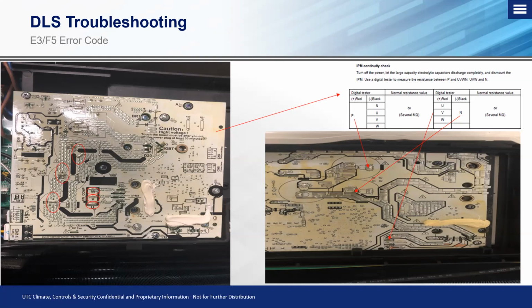These systems do not do well on power spikes or being run off of non-inverter generators. So that's one of the things that these capacitors help do, in line with the reactor or the inductor, which is essentially a choke, which helps filter that DC voltage and clean it up, take some of the electrical noise out of it. So that's how we're going to check the IPM board on a split type application.